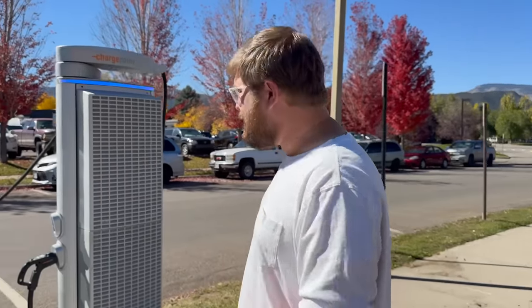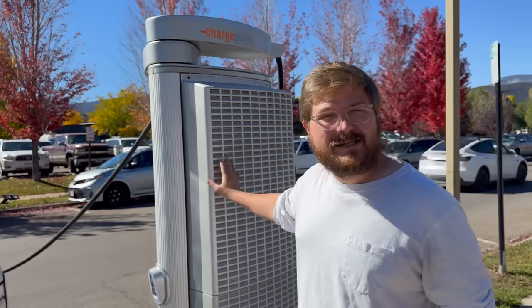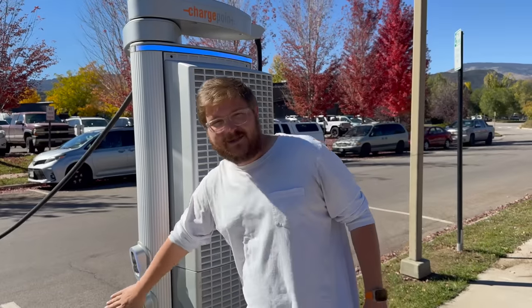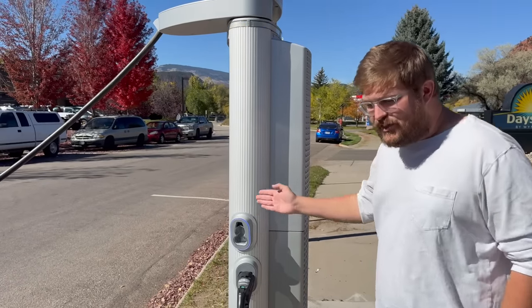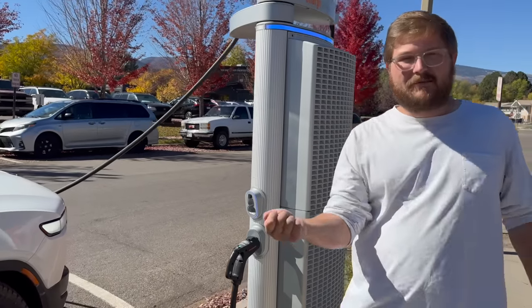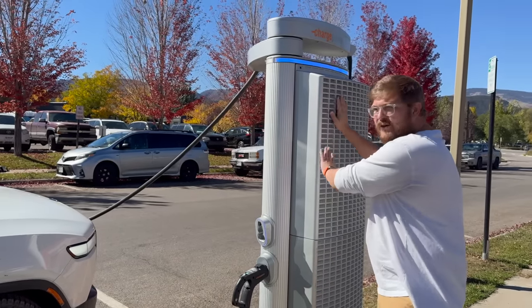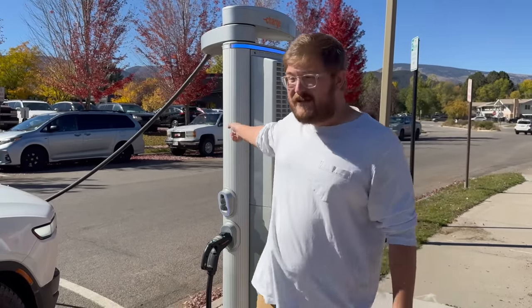What's interesting about this particular installation is it's only hooked up to 50 kilowatts maximum. It has plenty of power to pull from the grid — I don't know why they wouldn't go to the maximum output of 62.5 kilowatts, but maybe there will be upgrades in the future. Generally, you'll find the ChargePoint Express 250s available in a CCS and CHAdeMO configuration up to 62.5 kilowatts. Many installations include two units, and you can run a DC link between them to crank them up to 125 kilowatts — essentially doubling the power. The main problem in those configurations are the cables, which are quite thin.